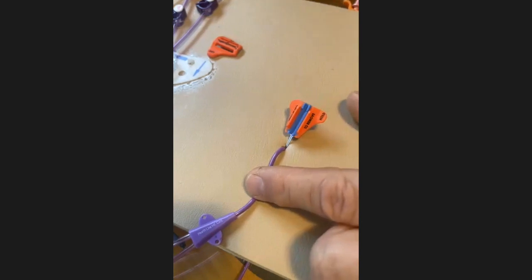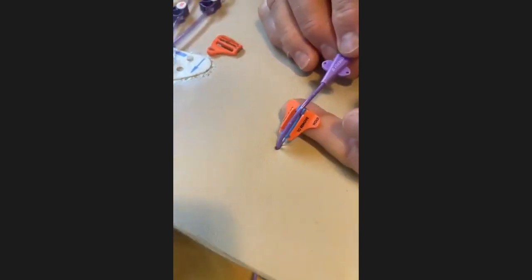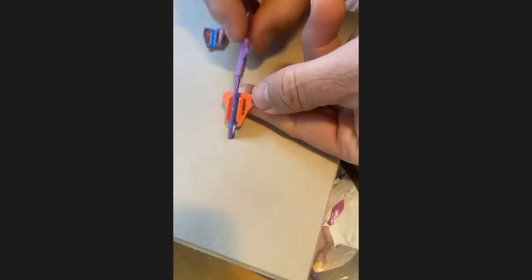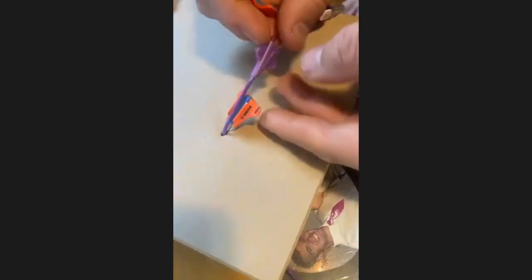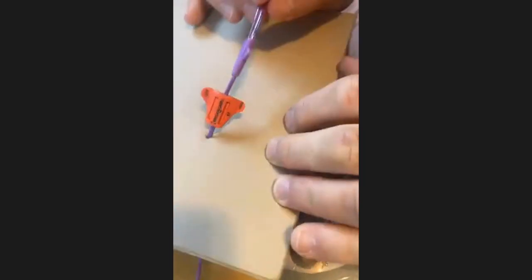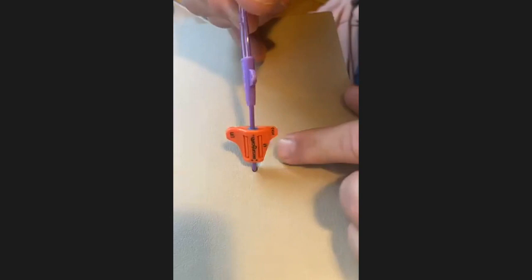Laura adds an important point for newer users: as you place the catheter in the blue channel, make sure the numbers are aligned and that the wings of the catheter and the wings of the SecurAcath are in the same plane. A common issue with newer accounts is that the wings are crisscrossed. When the lid is closed with the purple wings out of alignment, users try to flatten them, which creates a mechanical occlusion.